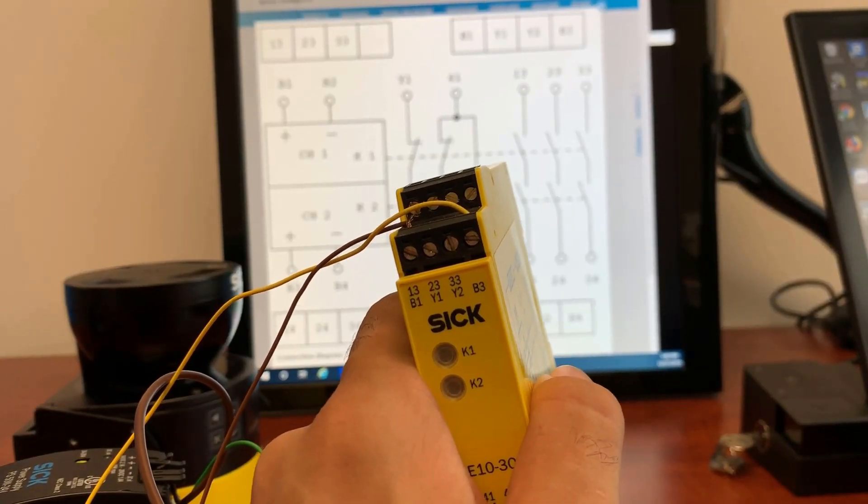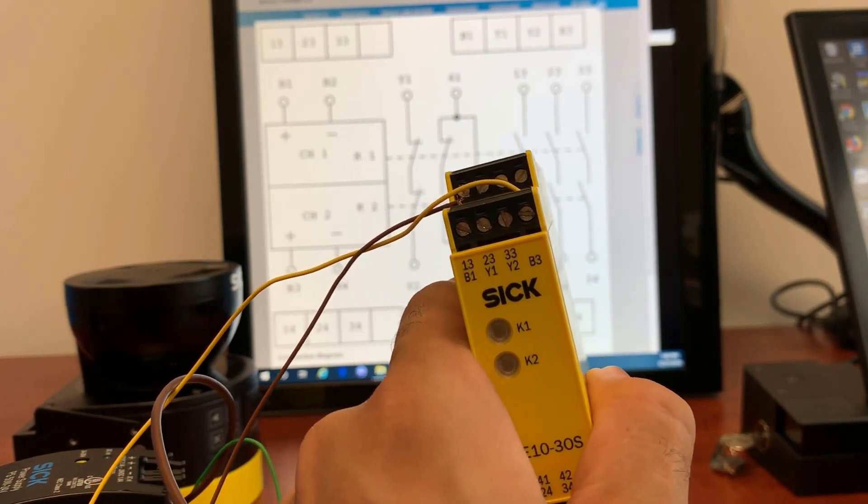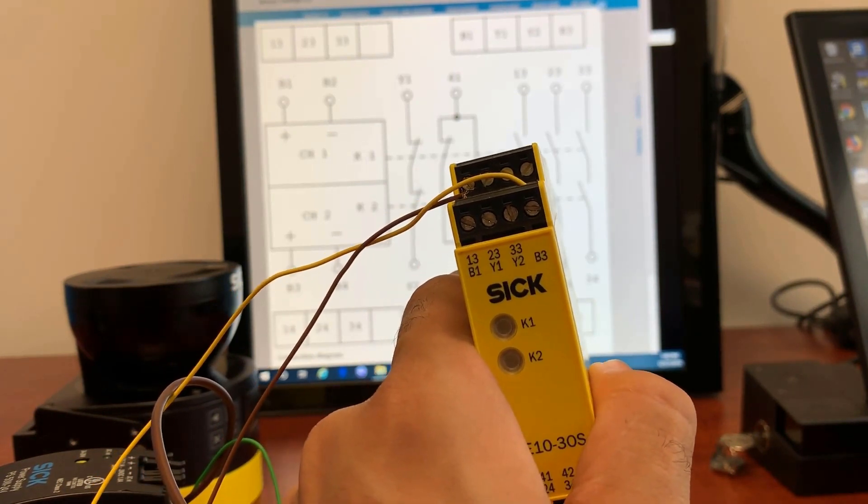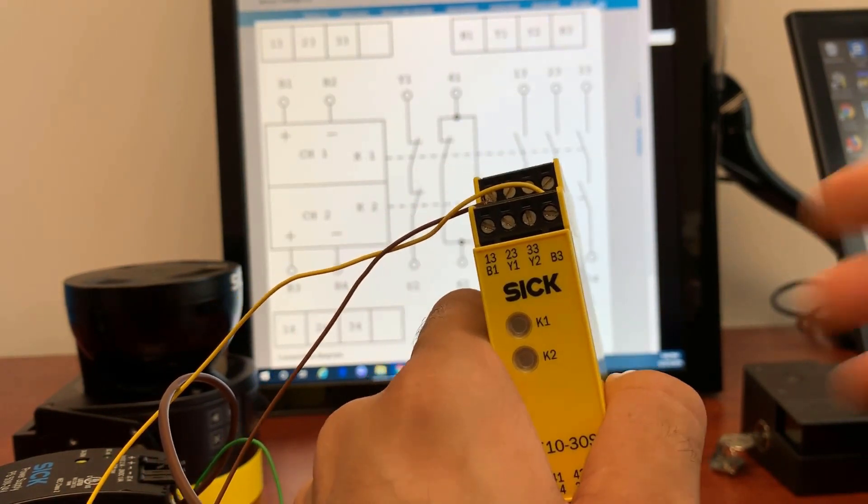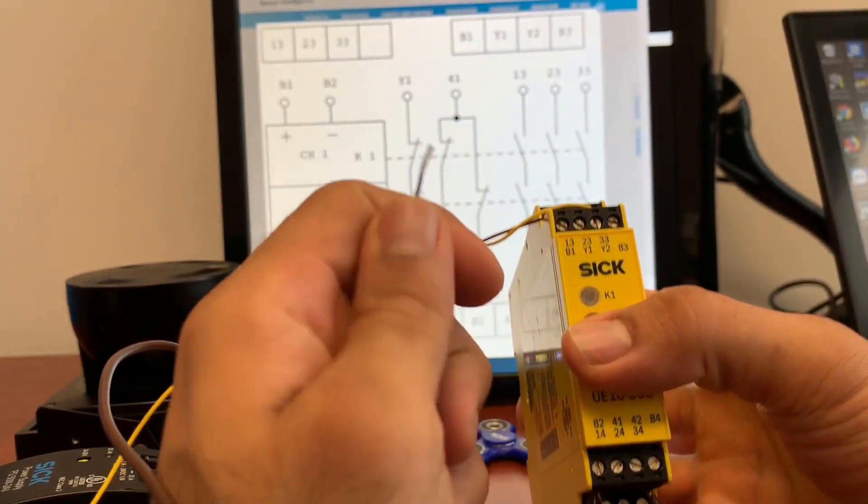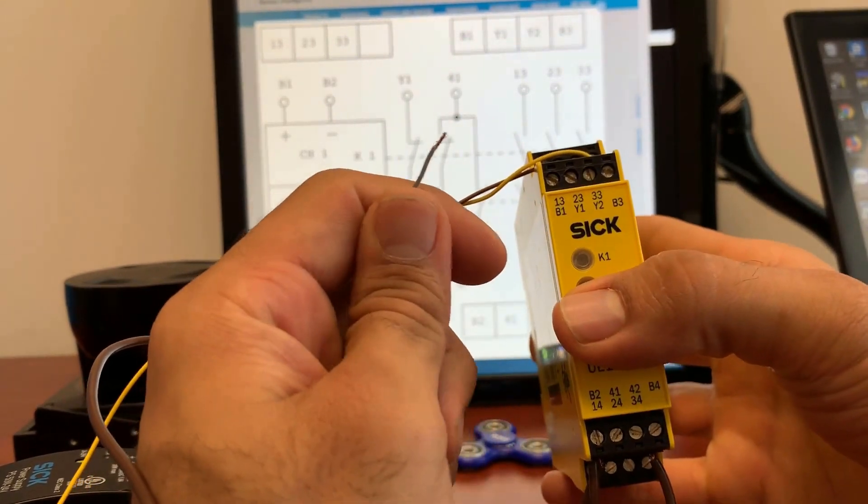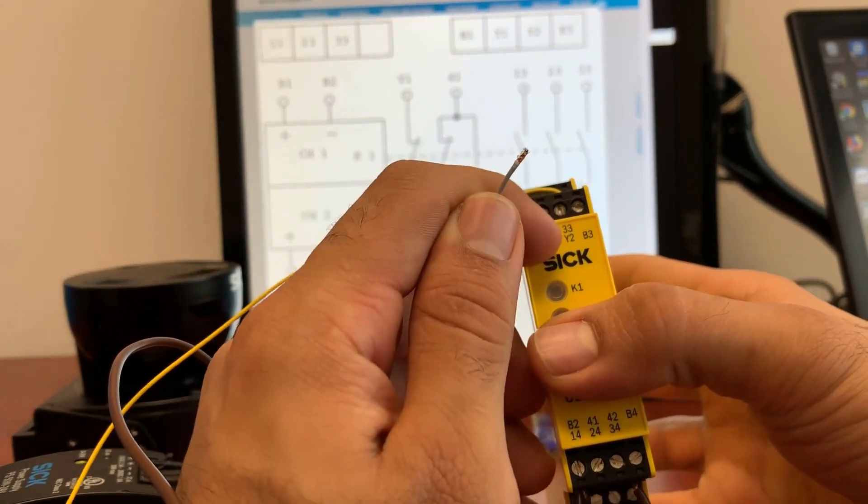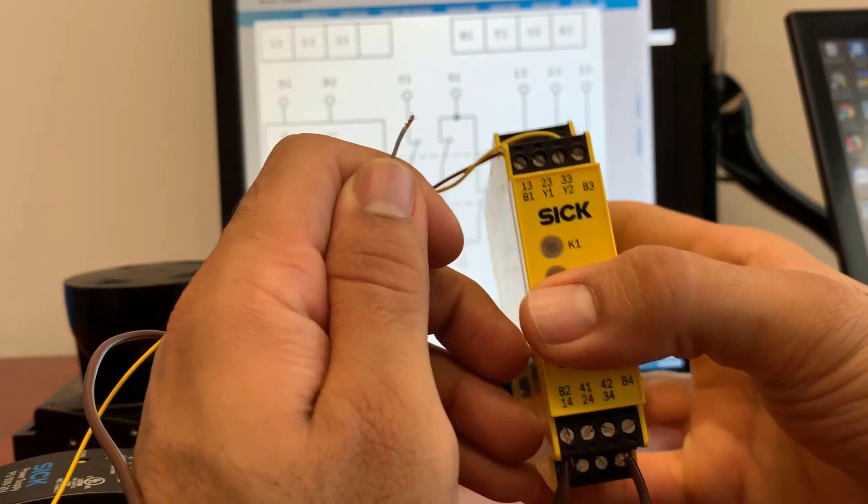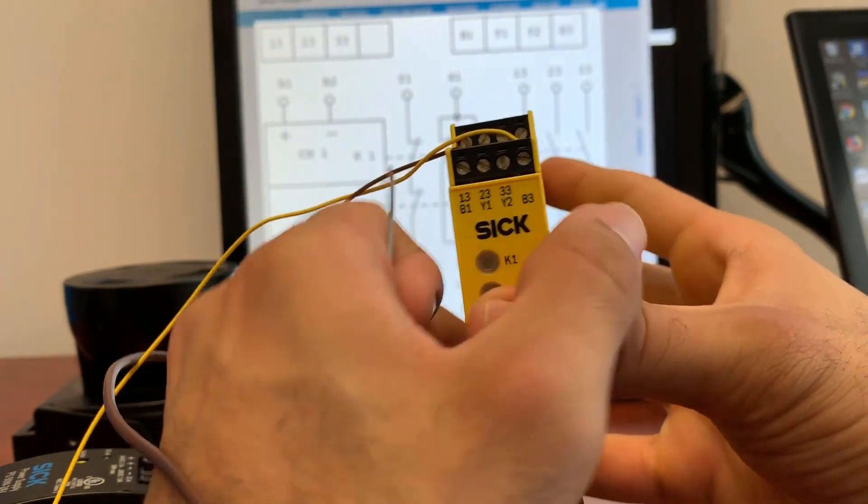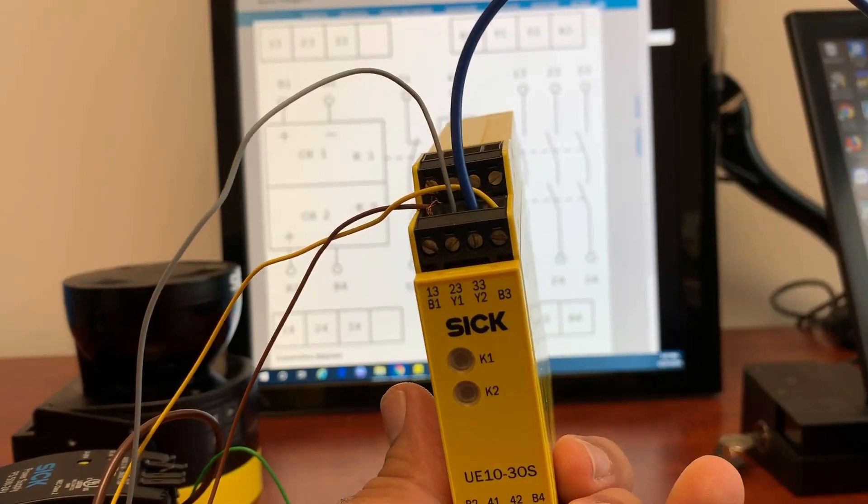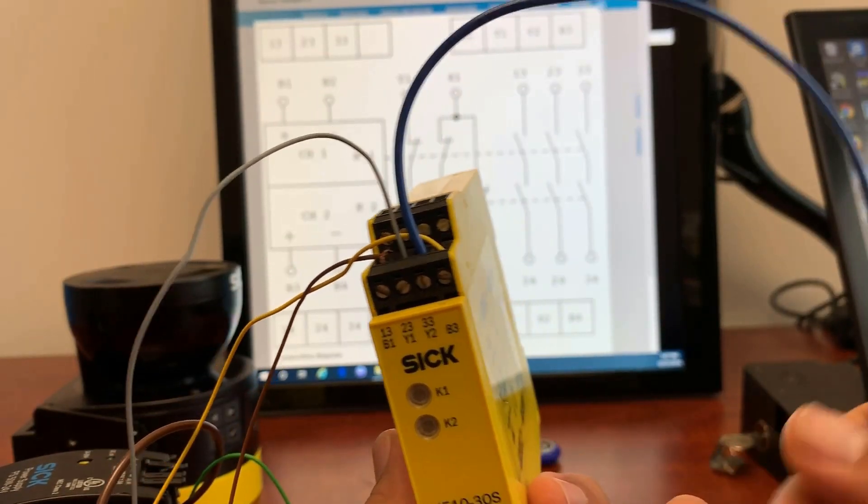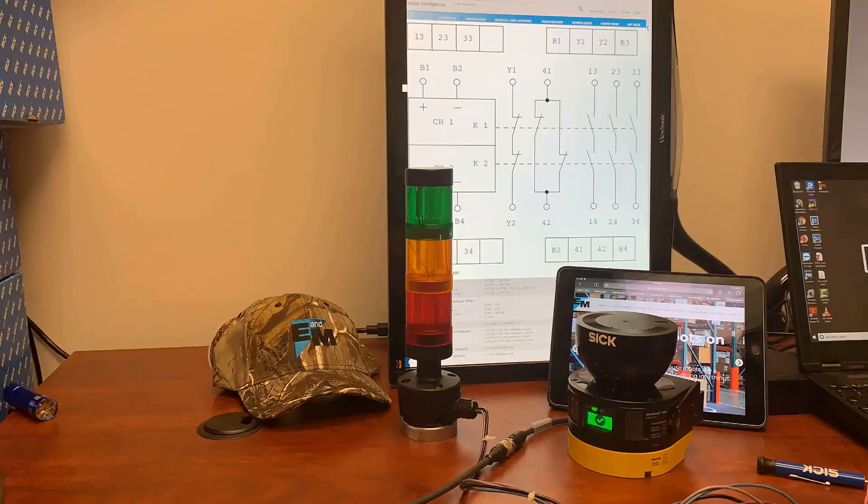Since this is not a self-checking relay, we would use EDM and we would connect the Microscan's input one for which I have configured EDM input and I'll give it to Y1 and Y2 would be given 24 volts. All right, that's connected and now we would give the Y2 to 24 volts.